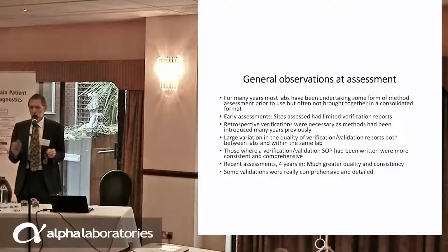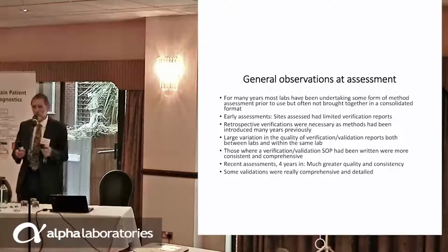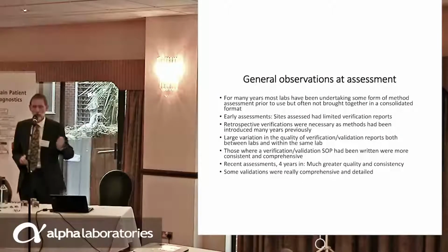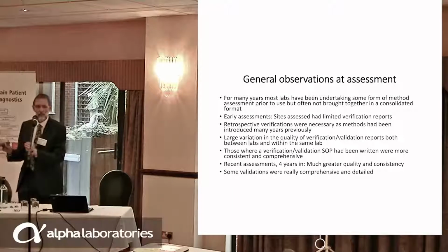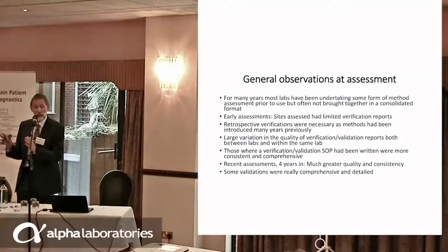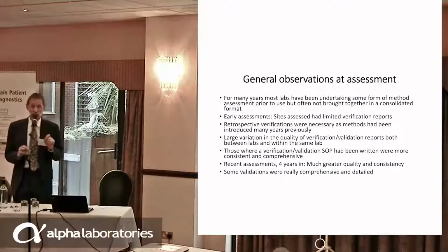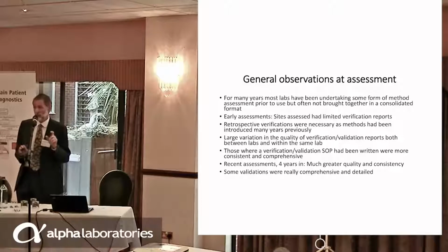I've had a variety of responses, from a fantastically written up verification through to a filing cabinet pulled out, with some printed off data from an Excel spreadsheet with 11 compared results for urea with no clinically abnormal results, and they said, look, they compare. Now, that is when you start saying, actually, I think you've got a finding here, that you haven't properly done that, okay?